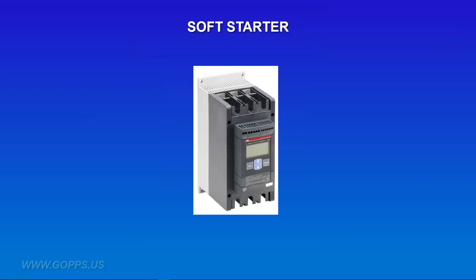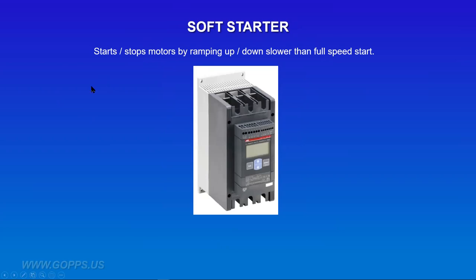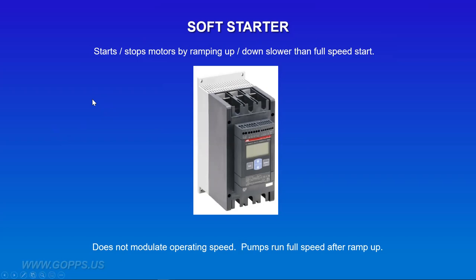A soft starter is a device that starts and stops a pump by ramping it up and down slower than full speed. If pressure drops in the main line, the pump ramps up slowly, and when pressure reaches a certain point, it ramps down slowly. This is easier on the pump and on pipes and fittings in the field. However, a soft starter does not modulate operating speed — once it ramps up to full speed, it continues at full speed. The only other operational option is that when pressure reaches a certain point, it ramps back down and stops.